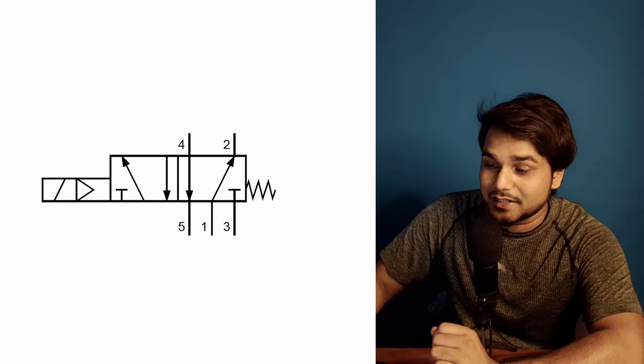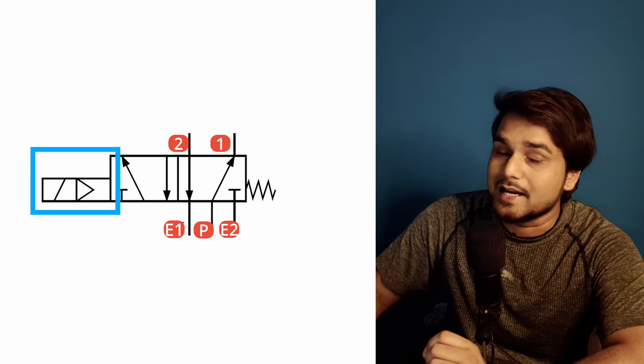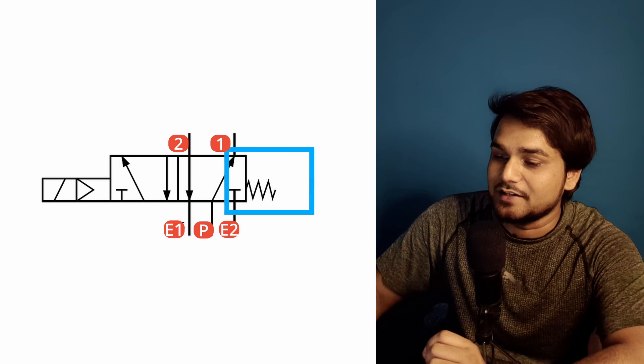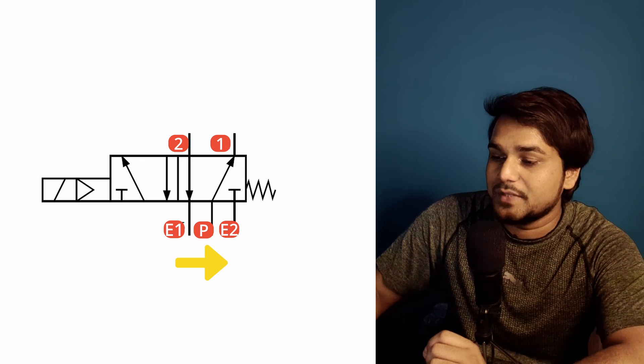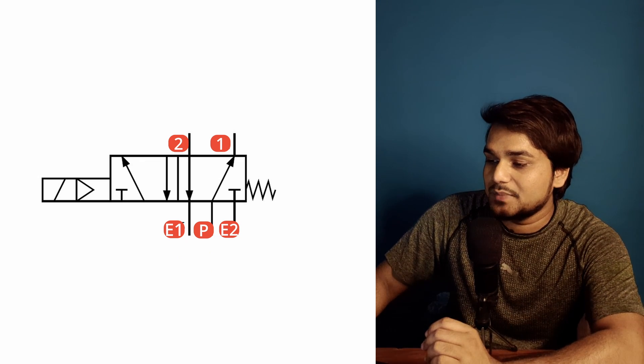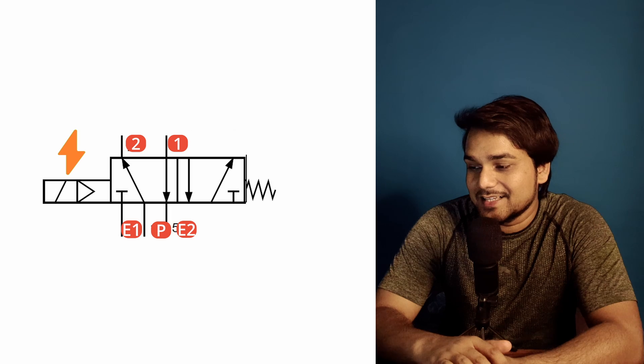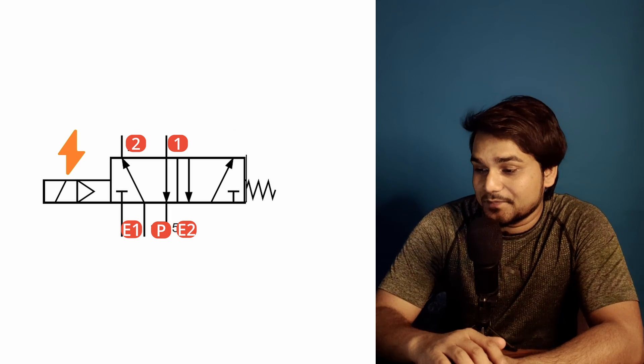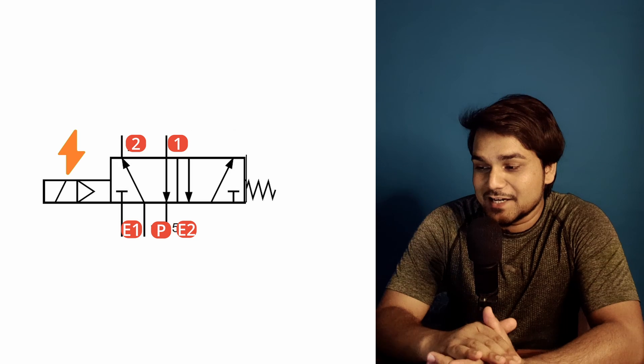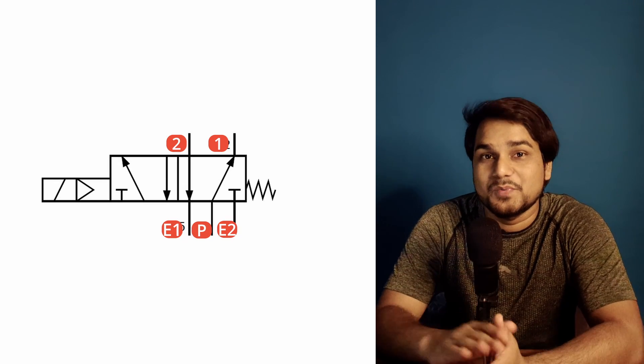In a 5/2 single coil solenoid valve, there is a solenoid only on one side and a spring return on the other. By default the valve spool shifts to the spring side, supplying air to port 1. It won't change position unless an electrical signal is supplied to the solenoid — but that signal must be kept continuous, otherwise the valve returns to the default position due to the spring return. This consumes more electrical energy, but saves one PLC output since there is only one solenoid.